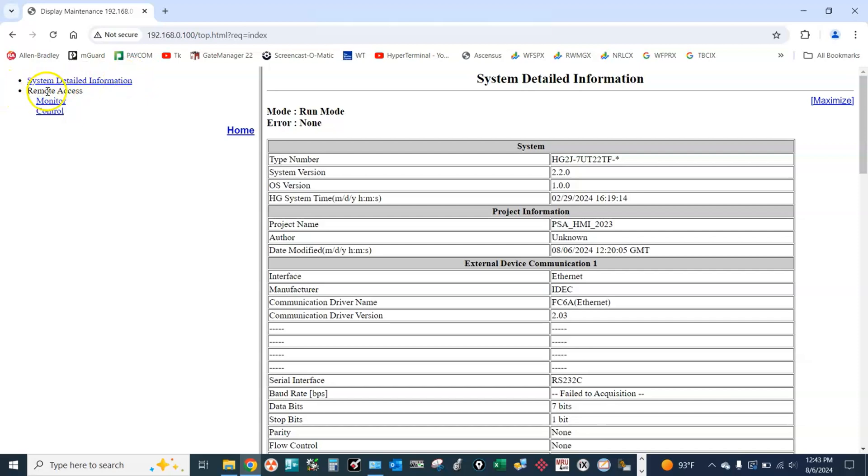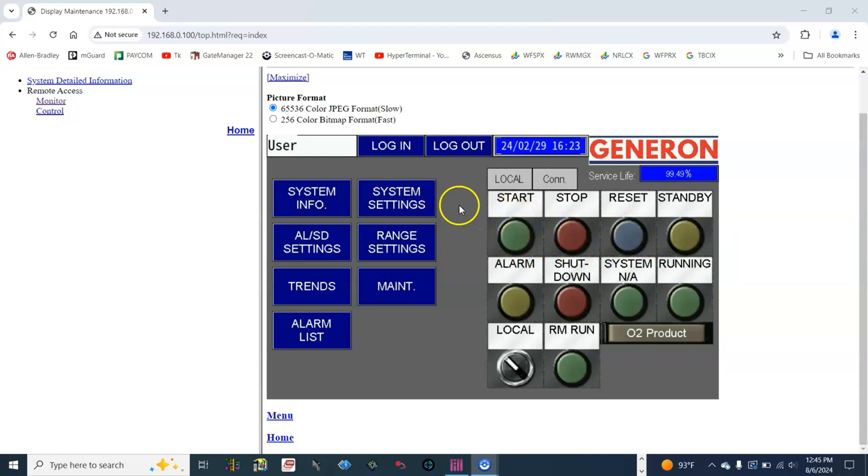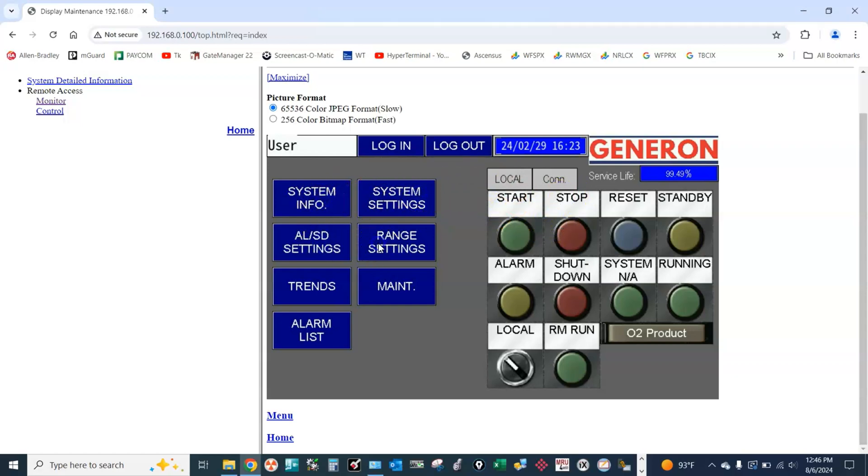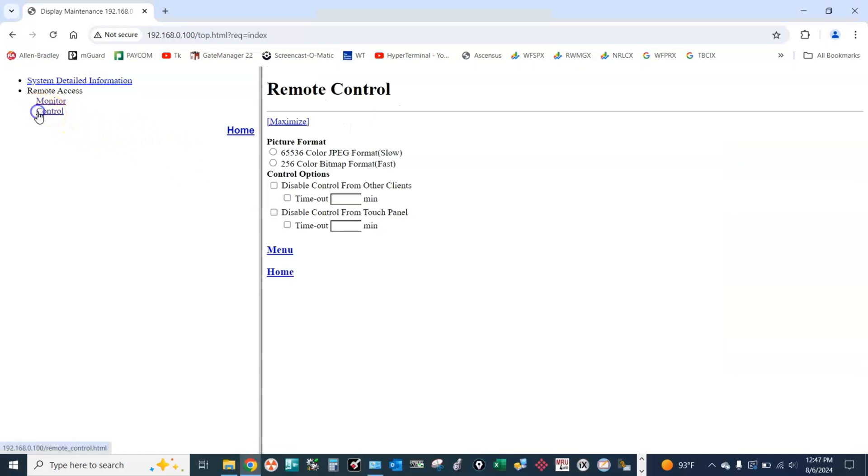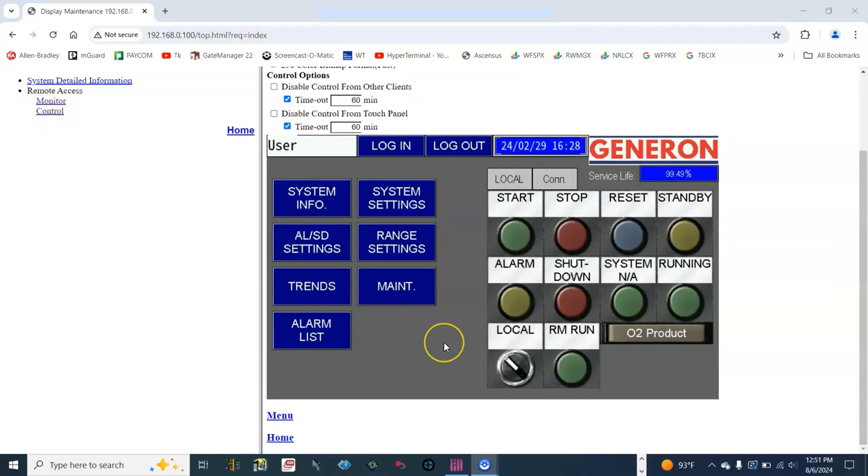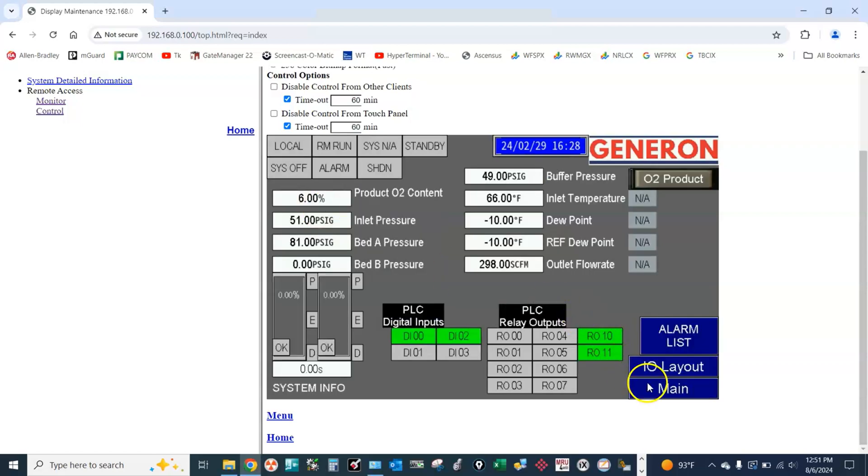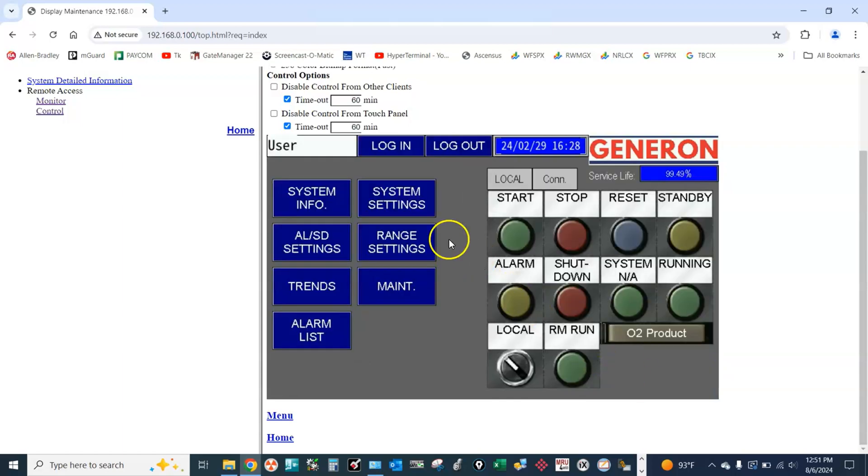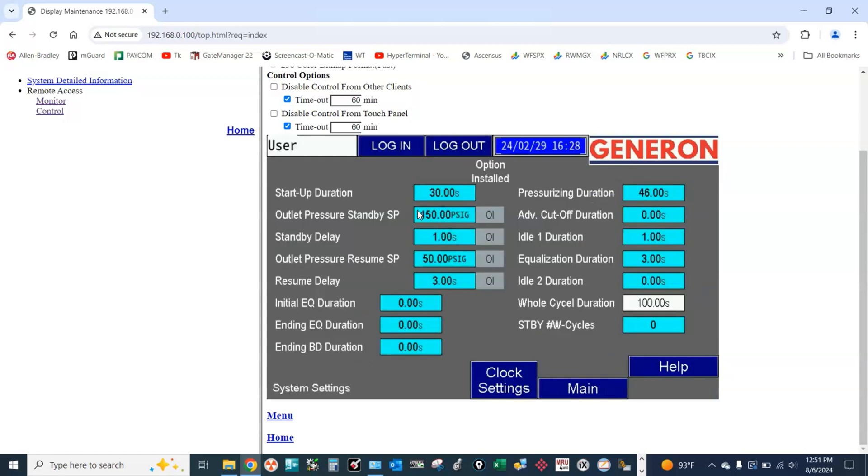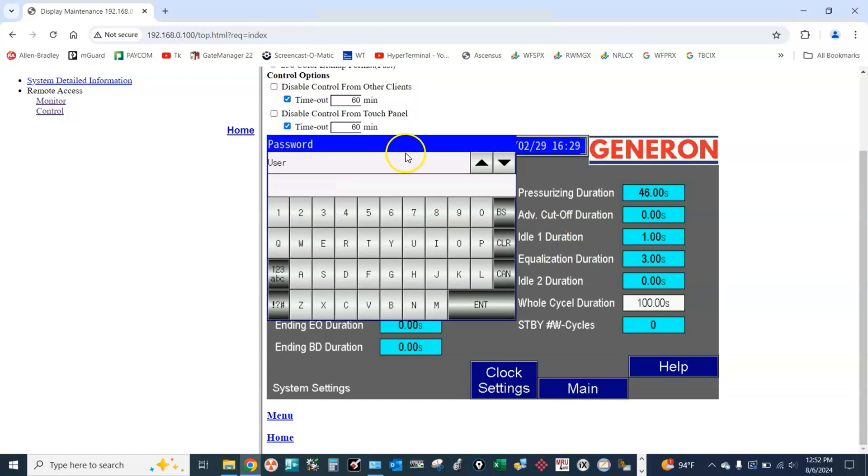For remote access, we have two options. Monitor - if this is selected we can only see statuses and readings on the HMI; we cannot even go to different screens. However, if we select the other option for control, we now can go to different screens on the HMI - system info, system settings - and we can also change the settings on the HMI.